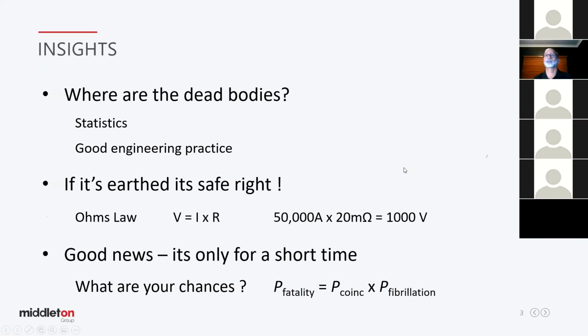So if we have an earth fault of say 50,000 amps, which is pretty high, but it's not unusual, through a 20 milliohm resistance, we find we've got 1,000 volts. So it's a very low resistance, but due to the high currents involved in earth faults, we can have some pretty high voltages on fences, on HV equipment, etc. Perhaps even on the taps in your houses.